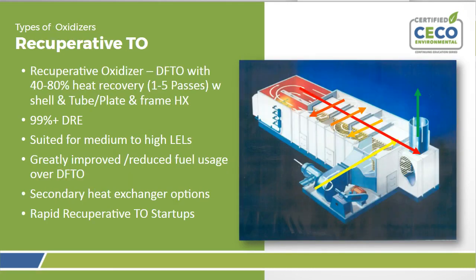Moving forward, a little more complicated, the recuperative thermal oxidizer. This is essentially a souped up DFTO. It has all the same components, only now you have a bit of heat recovery in the form of a single or multi-pass, usually shell and tube, heat exchanger. So what this does is preheat the process air using the hot combustion chamber air, recovering anywhere from 30 up to 80% of the total heat of the system in a really efficient system. In this image, the 4 parallel arrows indicate the flow path through the 4-pass heat exchanger. You can see it goes back and forth.